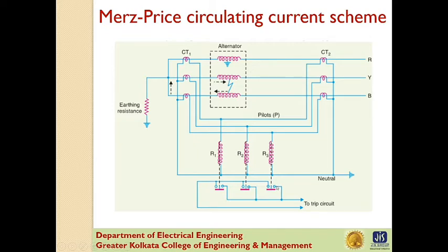Then the relay closes its contacts to trip the circuit breaker. It may be noted that the relay circuit is so arranged that when energized it causes, first, opening of the breaker connecting the alternator to the bus bar, and second, opening of the field circuit of the alternator.